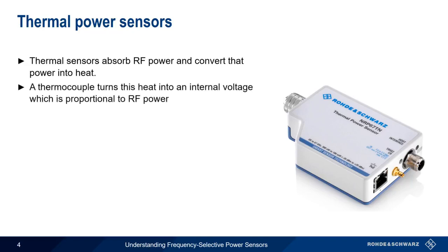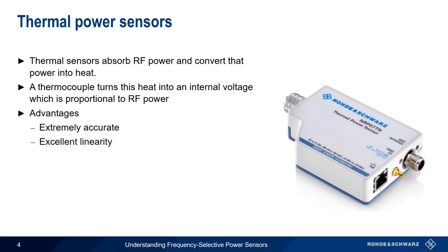We'll start with thermal sensors. Thermal sensors measure RF power by absorbing it and converting it into heat. A thermocouple then turns this heat into an internal voltage that's proportional to the RF power. The biggest advantage of a thermal power sensor is that it's extremely accurate, and they also have excellent linearity, making them the sensor of choice when high precision is required.